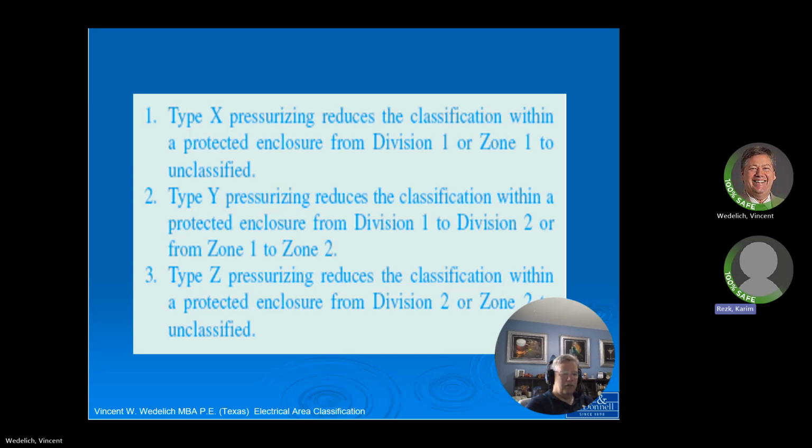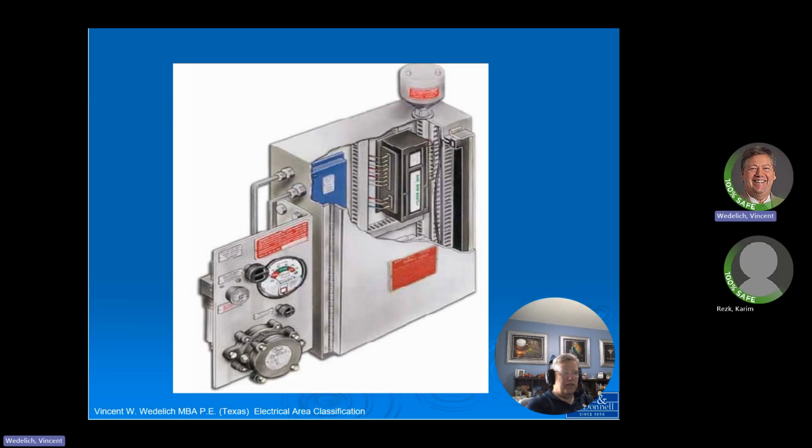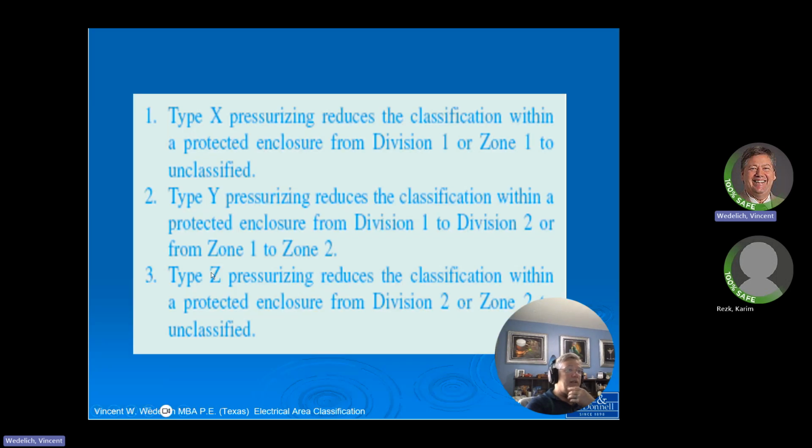Well, let me just see. You see this right here? If this was a PLC, like an Allen Bradley PLC, and I looked at the side of this, it would say it's rated for Class 1 Div 2. And terminal blocks are rated for Class 1 Div 2. And this, whatever this is, let's just say it's rated for Class 1 Div 2. Then you could put this box by itself with no Z purge system in a Div 2 area. But if you tried to put it in a Div 1 area, you would need a Y purge. You see what I'm saying?